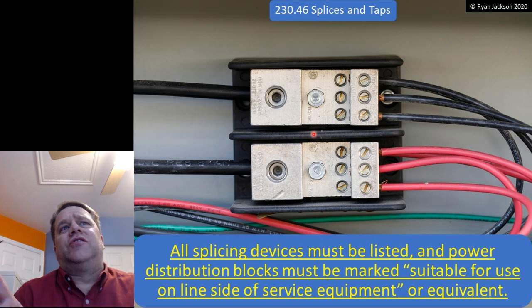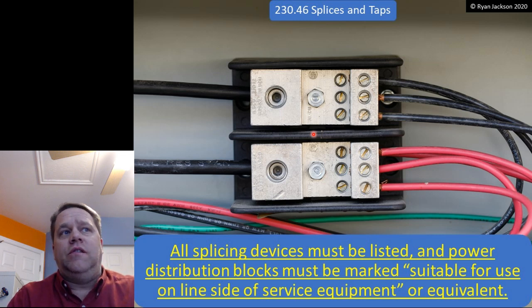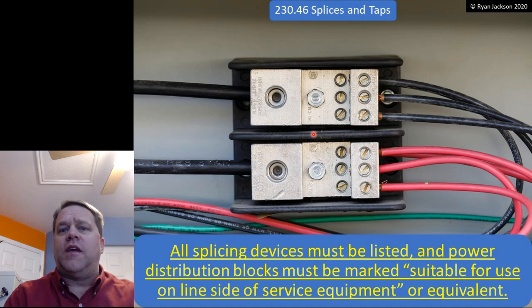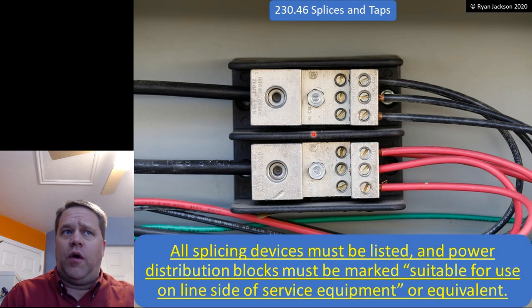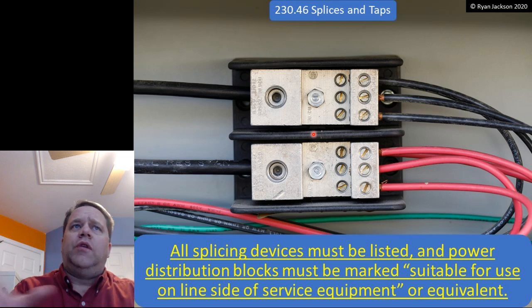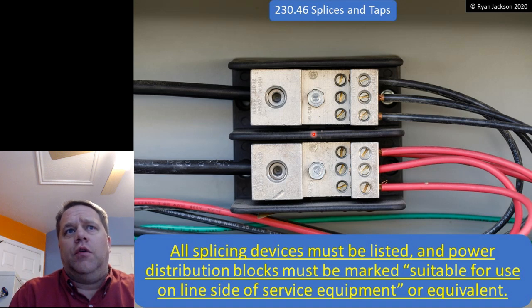Now, that actually isn't new. It was found in Article 314, I think it was in 314.28, if I'm not mistaken. But that only applies to large junction boxes. And it was also found in Article 376 for metal wireways, or what we often call gutters. But it was relocated here, which was definitely a good move.